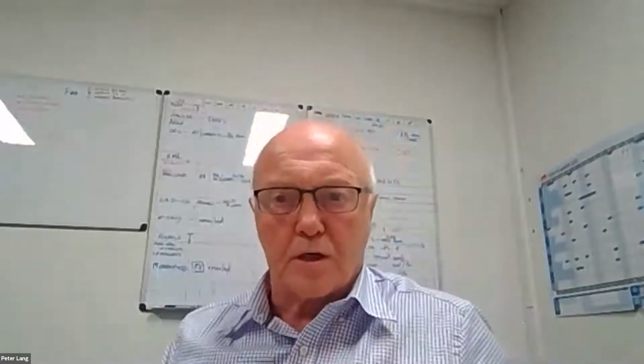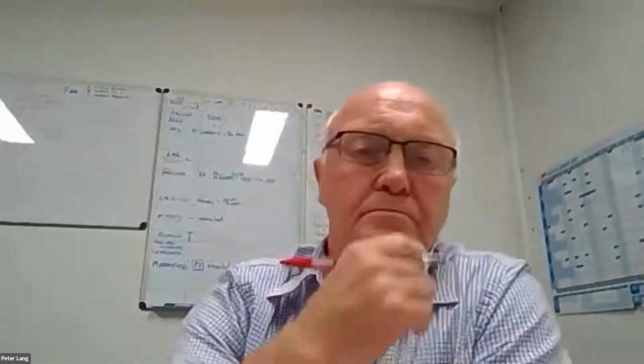Okay, just on that monitoring, I'm unsure whether Amit's looking at whether it needs to be monitored at the fire indicator panel. So that's possibly the question, but a fire damper obviously not. But for smoke spill, you'll find that it generally does have to be monitored at the fire panel, because often that's something that the fire department will be operating in the event of a fire in a building, and they'll need to understand what dampers are open and what dampers are shut with the smoke management system in the building.